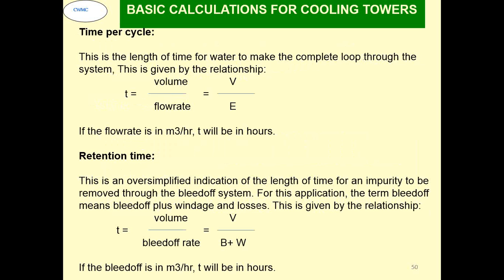Time per cycle is the time in which one cycle of the circulating water completes. It is equal to the total volume of the system divided by the circulating flow rate, V by F, with the flow given in meter cube per hour. The time will then be in hours.